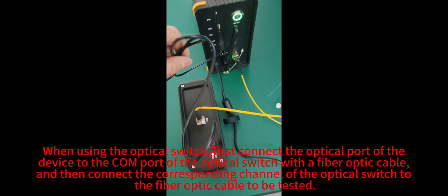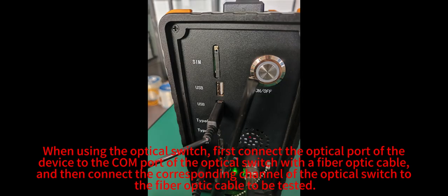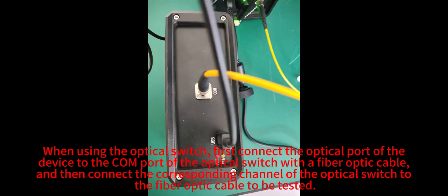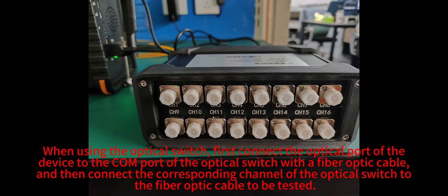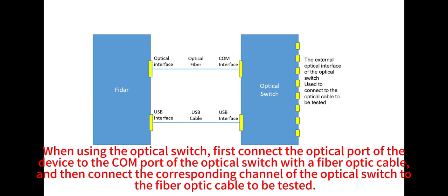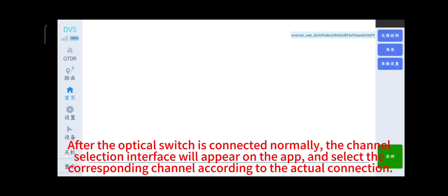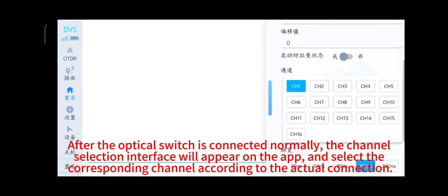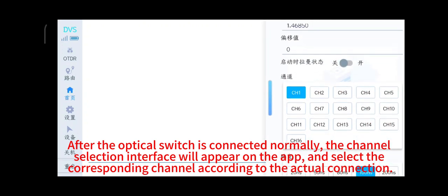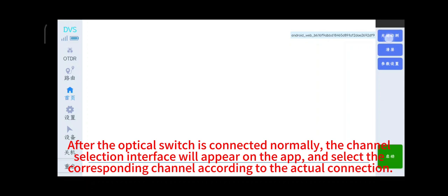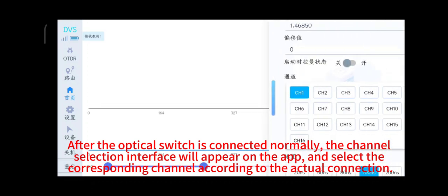When using the optical switch, first connect the optical port of the device to the COM port of the optical switch with a fiber optic cable, and then connect the corresponding channel of the optical switch to the fiber optic cable to be tested. After the optical switch is connected normally, the channel selection interface will appear on the app, and select the corresponding channel according to the actual connection.